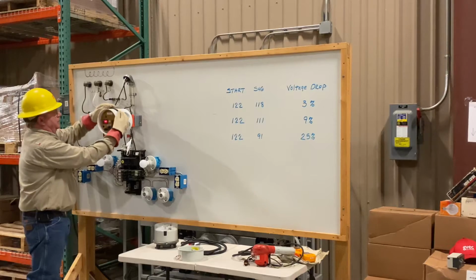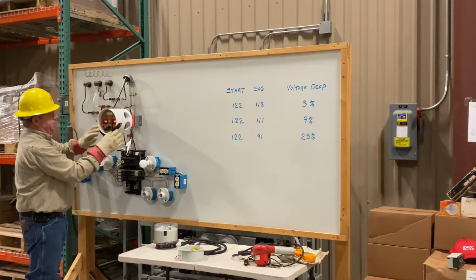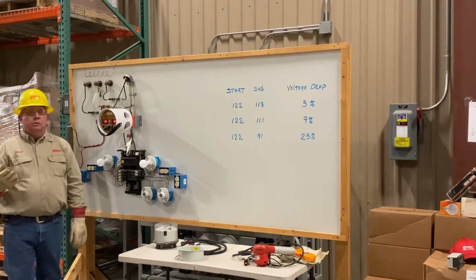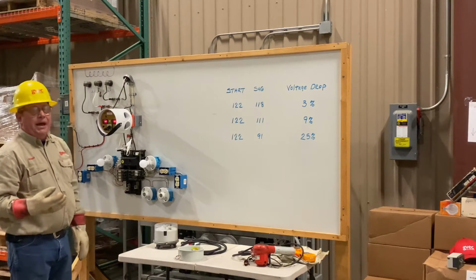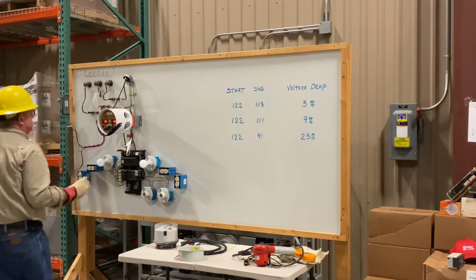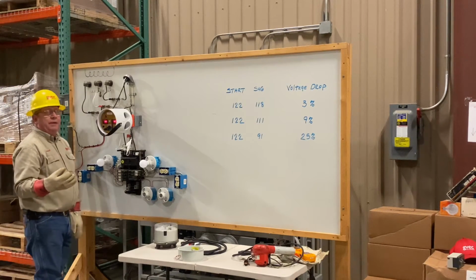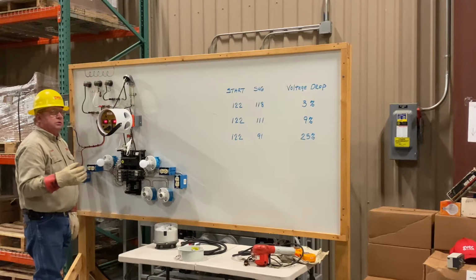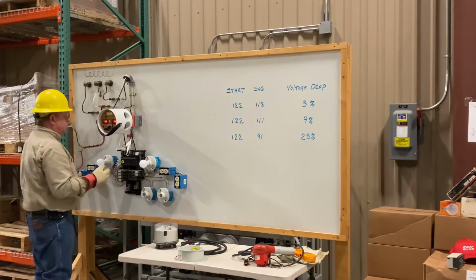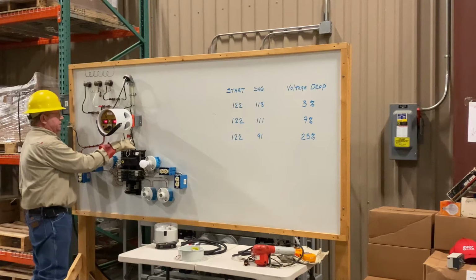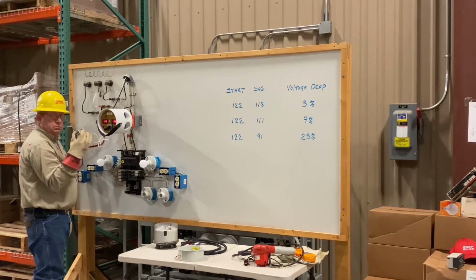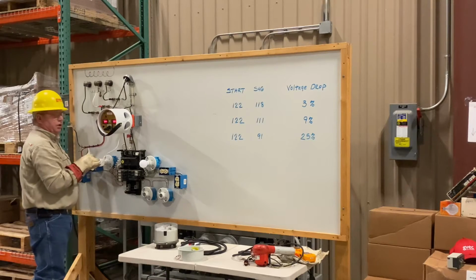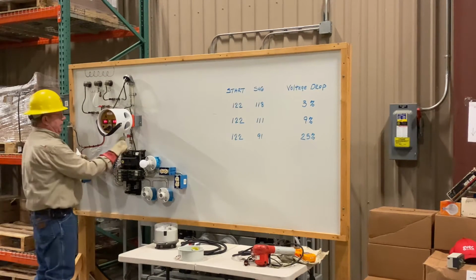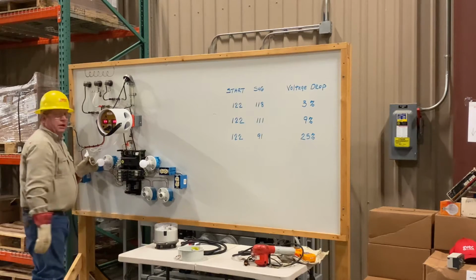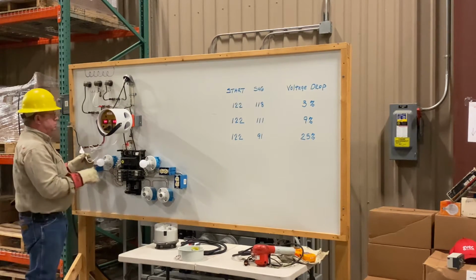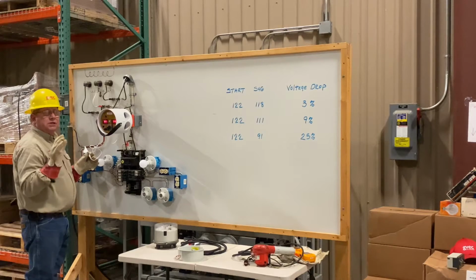I see voltage drop caused by wire length, but I do not see what you would call a bad neutral connector. Now, let's say this has been really bad for a long time and her neutral is almost gone. So if we put this in the wrong place, and what I'm going to do is I'm going to open the neutral connection going into her house.